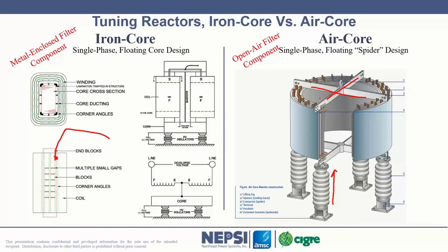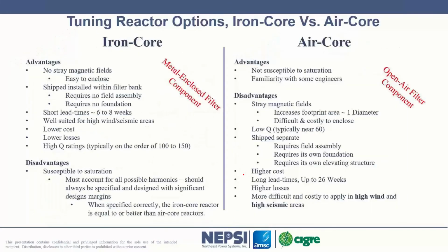So from an external view, the air core reactor has a very large magnetic field. If I have a fence over here, it's going to get magnetic heating, and you're going to get induced currents in it, and you're going to get heating. So air core reactors and the open air filter design require a lot more space. It's one of the reasons why some companies go with metal-enclosed harmonic filters. It's much more compact, typically about 20% of the footprint area.